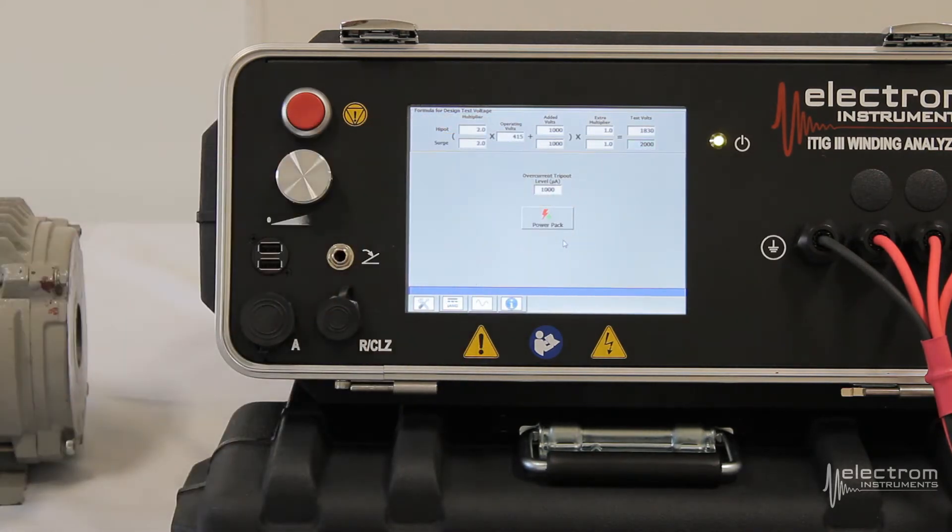Next thing here we have the over current trip out level. So that's essentially a safety feature during the megohm and high pot test. If the leakage current exceeds, in this case 1000 microamps, we'll shut off the test.